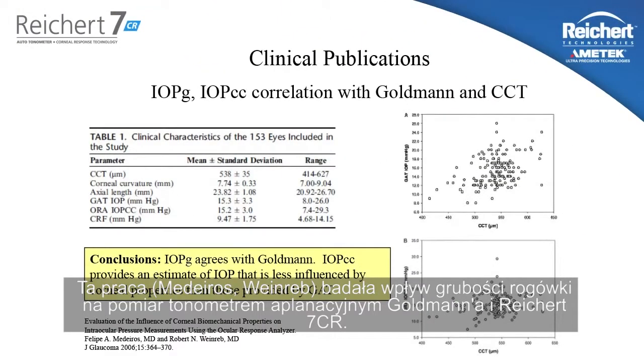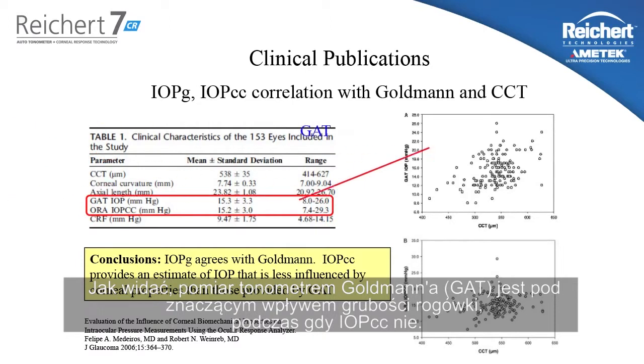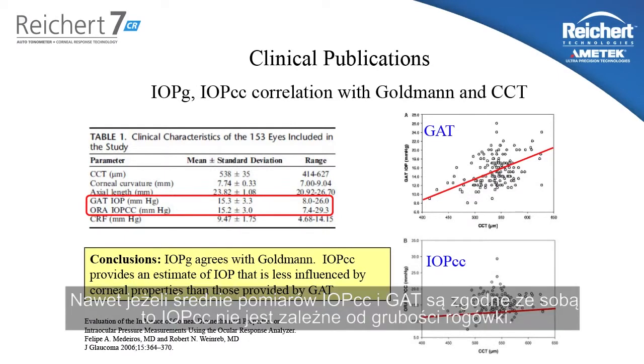This publication by Medeiros and Weinreb looked at the effects of corneal thickness on Goldmann tonometry and 7CR measurements. As you can see, the Goldmann tonometer is significantly affected by central corneal thickness, while the IOPCC measurement is not — even though the IOPCC measurement and the Goldmann measurement agree with each other on average.